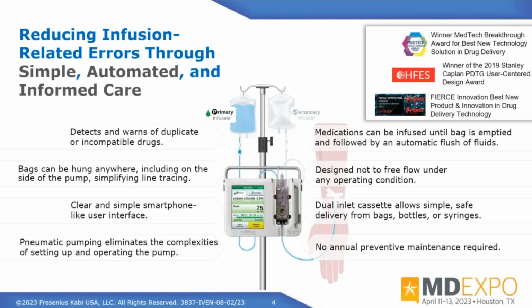Because of that calibration, there is no need to collect the devices annually and do preventative maintenance on them. If the team cleaning the devices inspects the devices for hardware damage, you know, tough love, right? Nurses are kind of hard on devices. Should the device be damaged, it would be returned to Biomed, of course. But if that inspection occurs during cleaning, then there is no reason to collect the device throughout the life of the device for a scheduled reason.